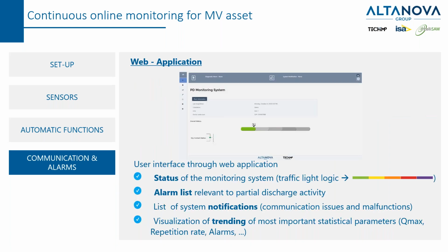The interface of the software application, as we mentioned, has different pages. The home page shows this color scale of PD detected. There is another page related to the alarm list, relevant to the partial discharge activity based on a historic of the unit, a list of system notifications, and, to go in more detail, the visualization of trending of the most important statistical parameters: amplitude, repetition rate, and alarms.